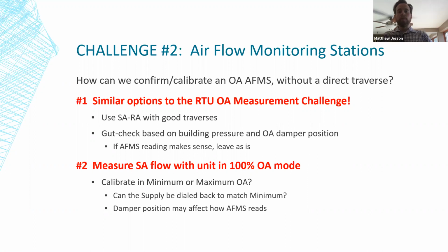So the question might be, what's more important, the reading when it's in minimum outdoor air or when it's at higher airflows? My expectation would be that it's usually more important to get that minimum correct, because that's when the CFM is important. And when it goes into economizer mode, it's really about maintaining the mixed air temperature. The exception might be if it's being used in a building pressure control sequence of some kind, where it might be important to have an accurate reading at the high end.